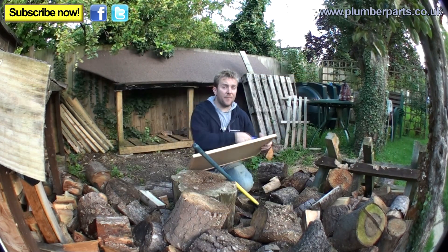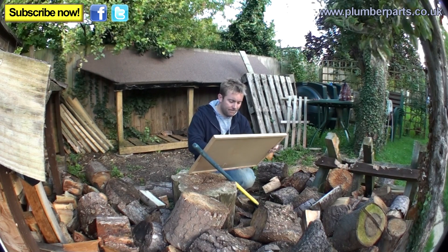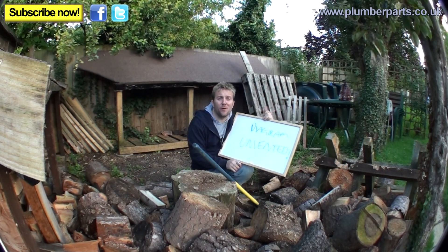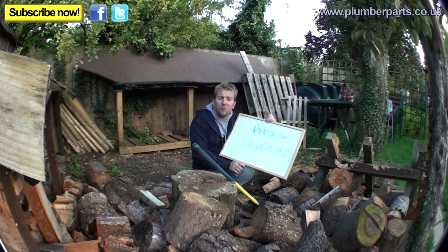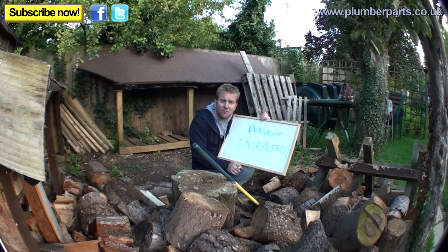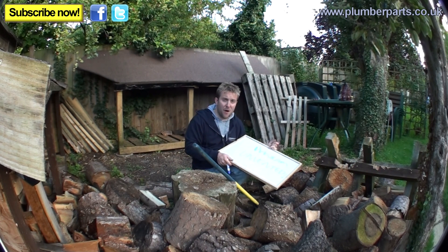Well Nick, I've thought long and hard about a diagram for this — it's really hard to put into pictures and words. Always go for an unvented cylinder. They're miles better than combi boilers — their flow rates are better, and if something goes wrong with the boiler at least you've still got hot water with your immersion as a backup. I always recommend them unless you've got like one bathroom, one kitchen, and it's a small flat, where combis are great. So go for a standard system boiler with an unvented cylinder — miles better, especially with that many rads and bathrooms.